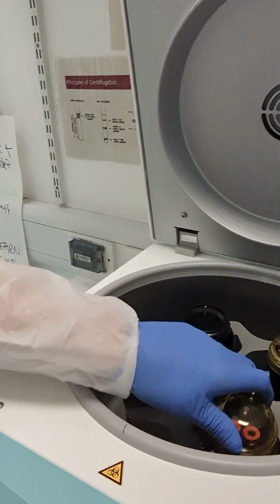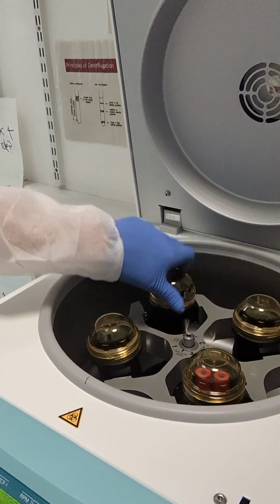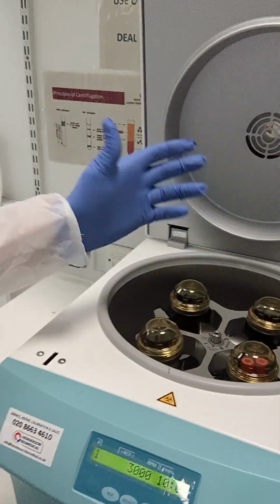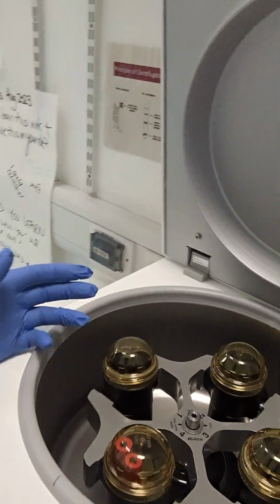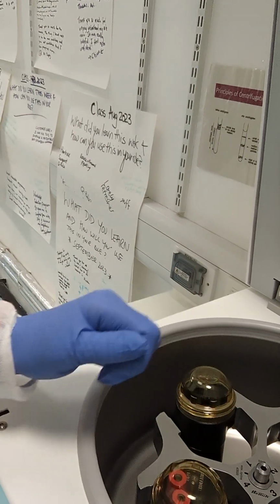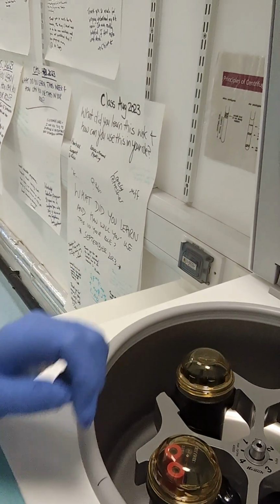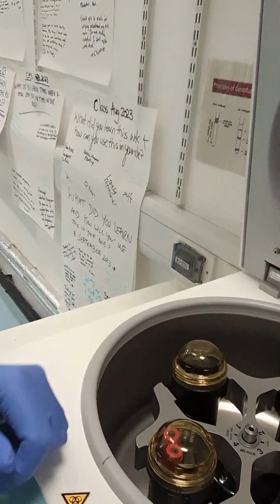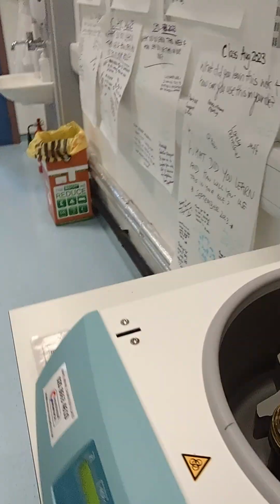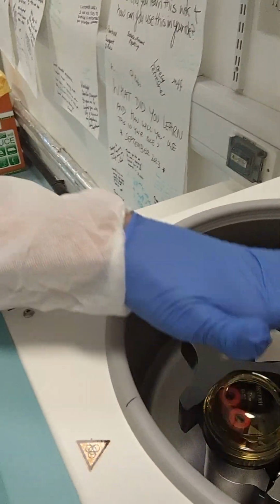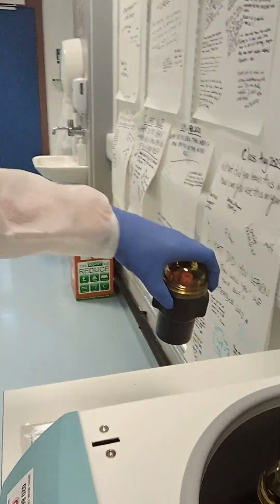So the first time you probably realise you actually have a broken sample is at the end of the cycle. There may be a noise during the centrifugation, you may not. But after the cycle has come to a stop and you've opened the lid, you'll notice that there's probably blood stains on one of the biolid seals, and it's probably quite apparent that one of the samples inside has actually broken. At which point you realise, okay, I've got a breakage. What do I do? Because you've used the biolid seals, the break will be contained to a single bucket. The affected bucket can be removed, put to one side, put a piece of paper beside it saying broken sample and a time on it, leave for 30 minutes.